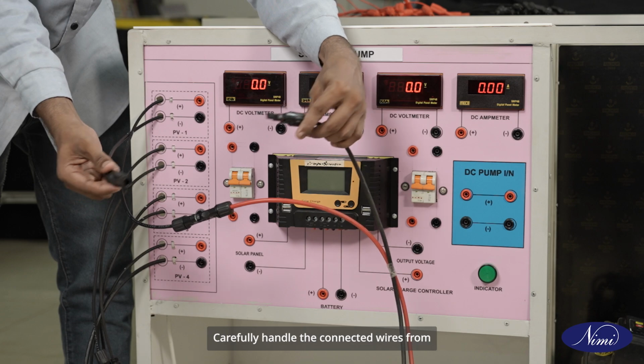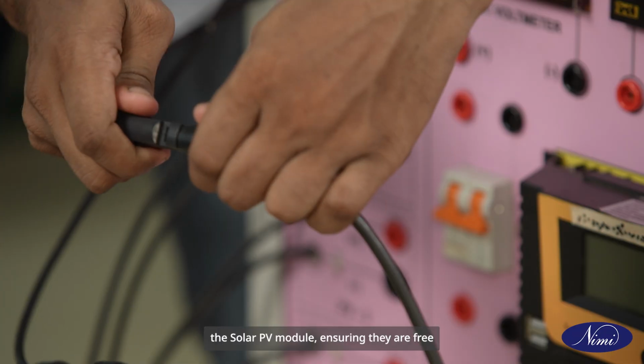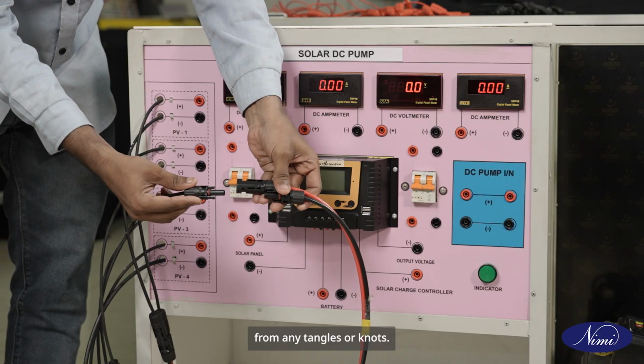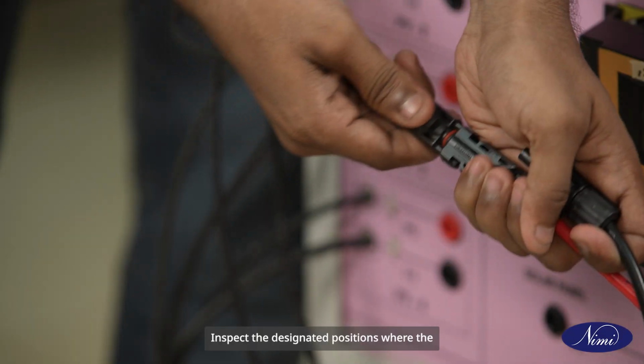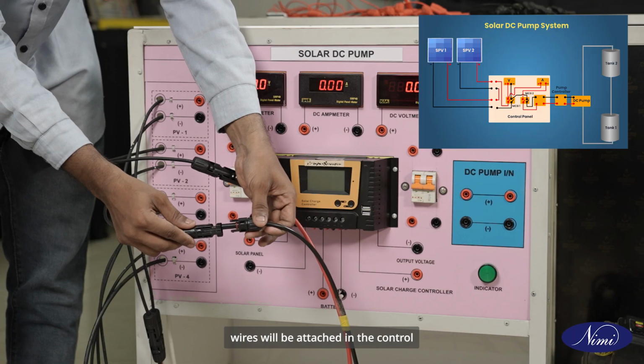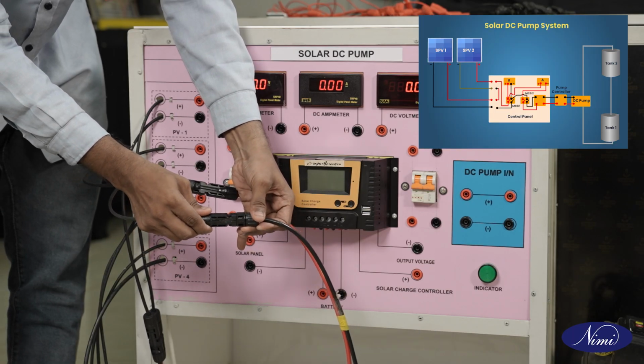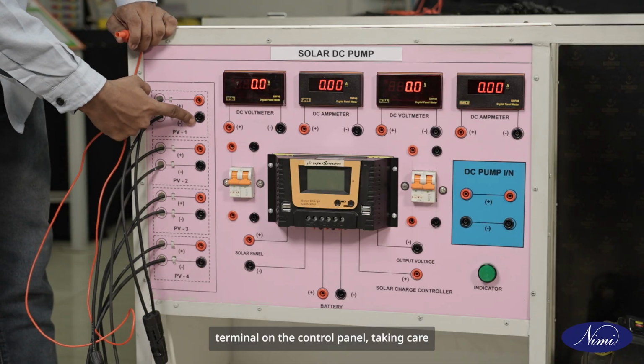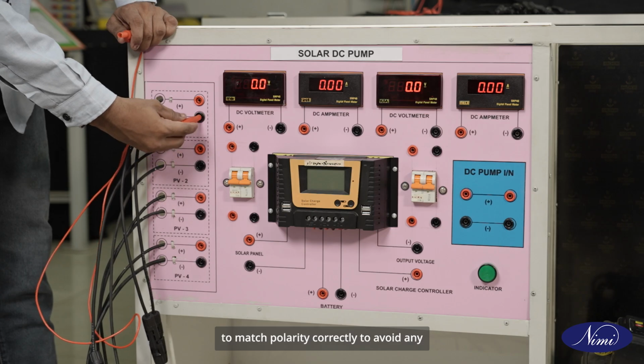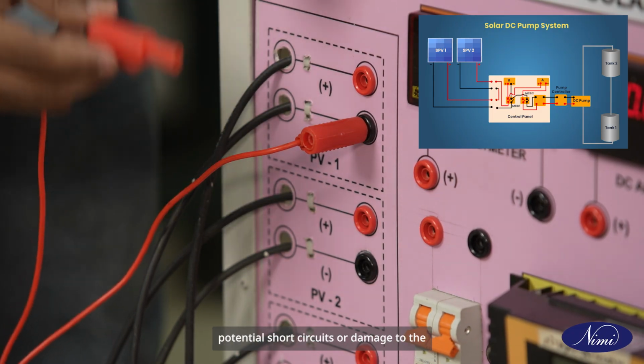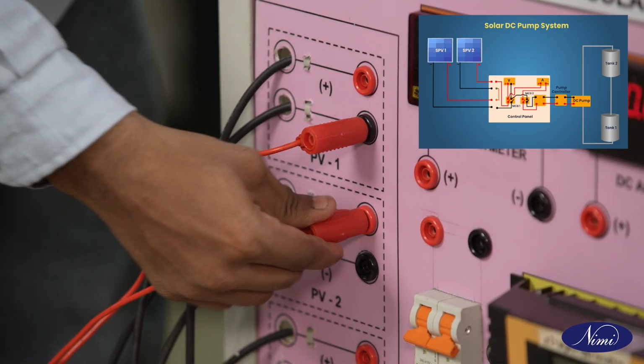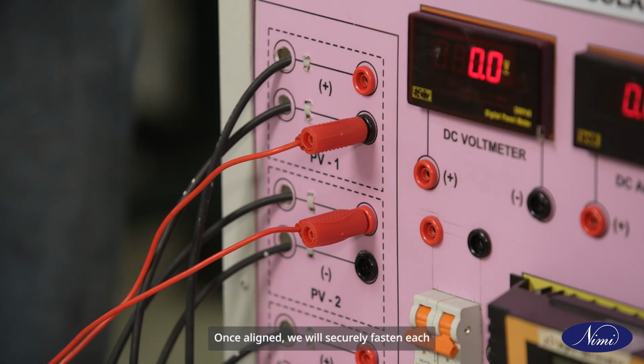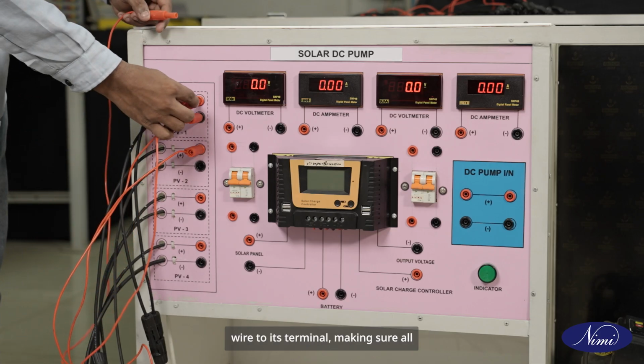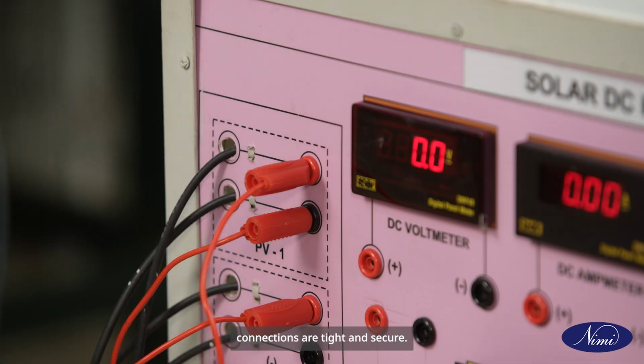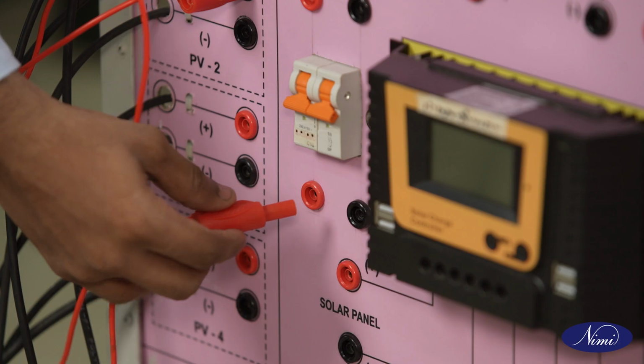Carefully handle the connected wires from the solar PV module, ensuring they are free from any tangles or knots. Inspect the designated positions where the wires will be attached in the control panel. Align each wire with its corresponding terminal, taking care to match polarity correctly to avoid any potential short circuits or damage to the system. Once aligned, securely fasten each wire to its terminal, making sure all connections are tight and secure.